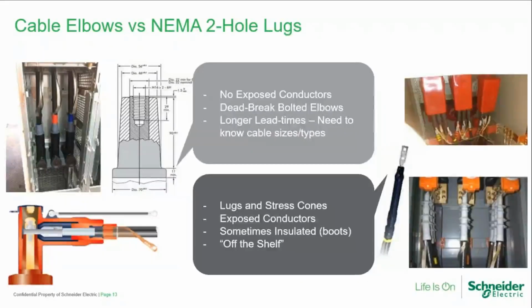Cable connections are changing. With these newer styles, the GIS and the SIS styles of switchgear, we look into using elbow styles of connection as opposed to the traditional NEMA 2-hole lug connections. The real big benefit here is that we're removing the exposure to potentially live components in the cable compartment. We're completely insulating even the connection point for the cables, which grants a huge benefit around safety and reliability. It also lets us shrink the footprint quite a bit of the entire switchgear package if we can move those cables a lot closer together.